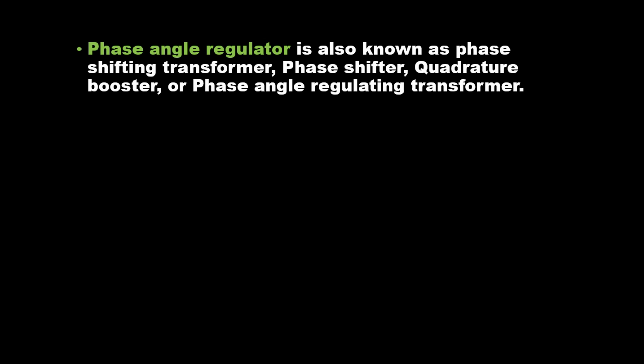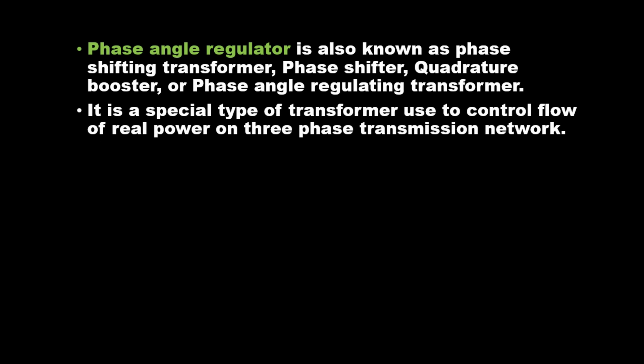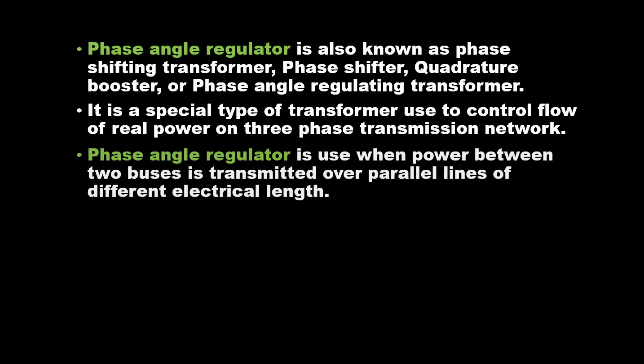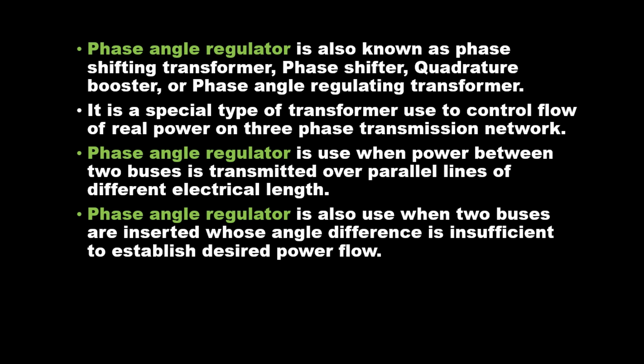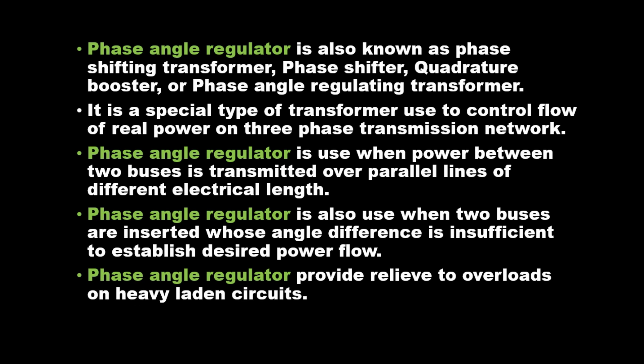It is a special type of transformer used to control flow of real power on three-phase transmission network. Phase angle regulator is used when power between two buses is transmitted over parallel lines of different electrical length. It is also used when two buses are interconnected whose angle difference is insufficient to establish the desired power flow.